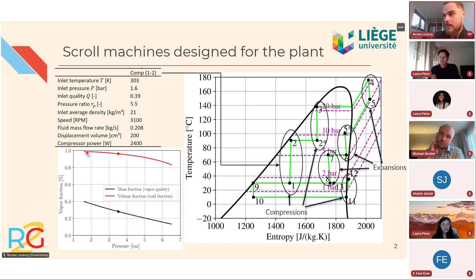Those are the prototypes that we have developed throughout the project. First, we experimentally tested the commercial compressors, and we modeled the commercial compressor working with two-phase refrigerant flows. With the outputs from the sensitivity analysis, we designed this scroll prototype, which has a high displacement volume, higher than the commercial machines that we can find, and a high built-in volume ratio, because we noticed that to get better efficiency with two-phase flows, such a high built-in volume ratio is needed. It has a radial compliance, so that if you have too much liquid stuck in the machine, you're not breaking the scroll mechanism, and you still have this compliance allowing the orbiting scroll to move.